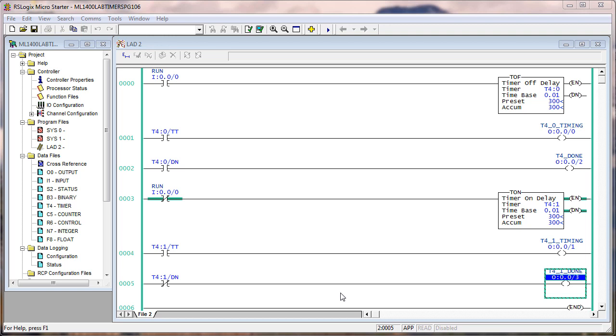What two changes did we make in the TON logic to make it behave like a TOF? Invert the state delayed from on to off, which is input zero. We delayed that. We inverted it. So we delayed, instead of delay on, we delayed off.